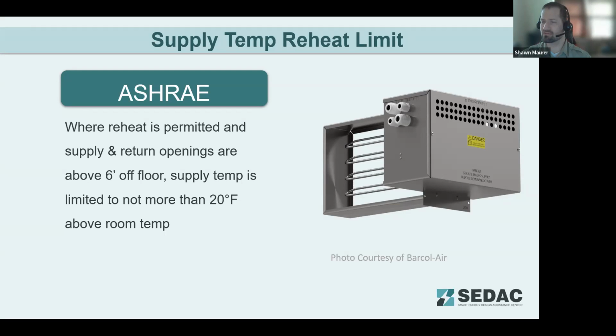Plays a role in both limiting reheat energy and reducing stratification that is normally compensated for with higher airflow in HVAC design. And so here what we're trying to look at with ASHRAE is some guidance on looking at the space temperature and looking at the delivery air temperature. What is the typical design condition that's not going to promote stratification of air delivered to that space, so we can both minimize the airflow going into that space but still maintain comfort while providing reheat to those areas.